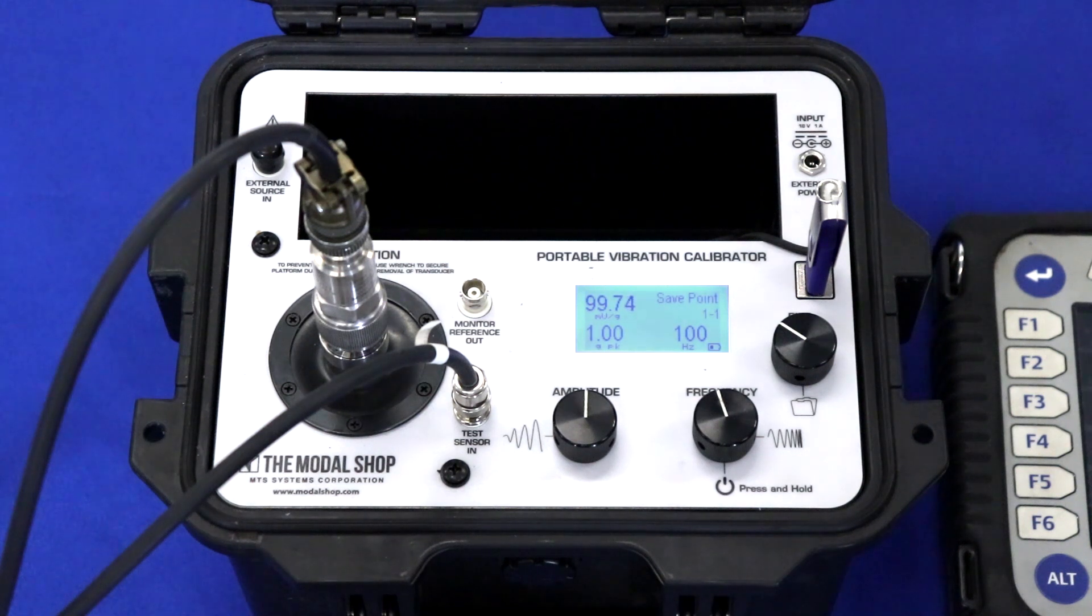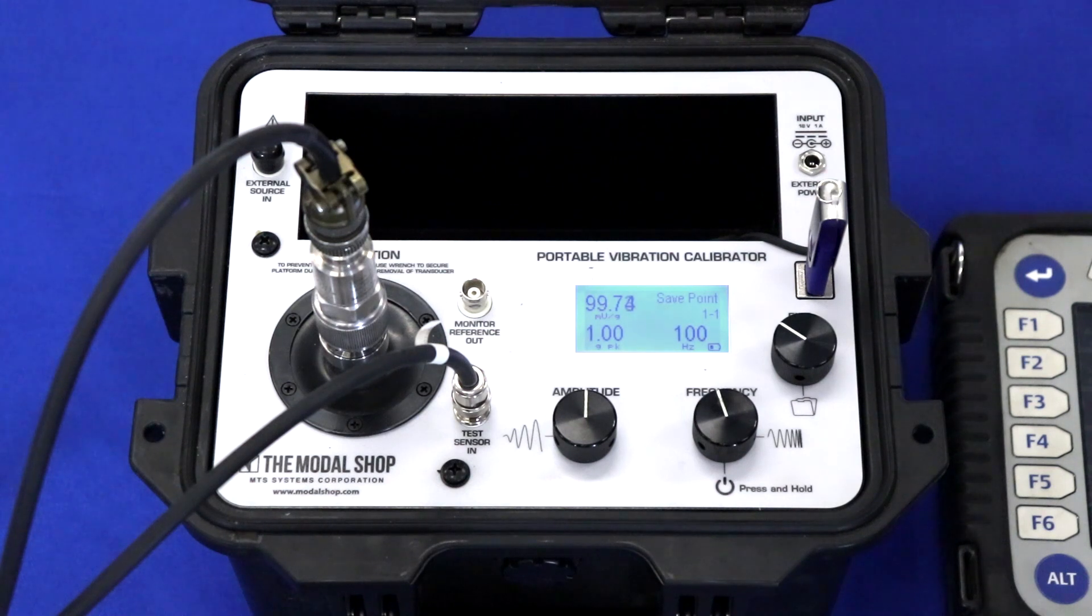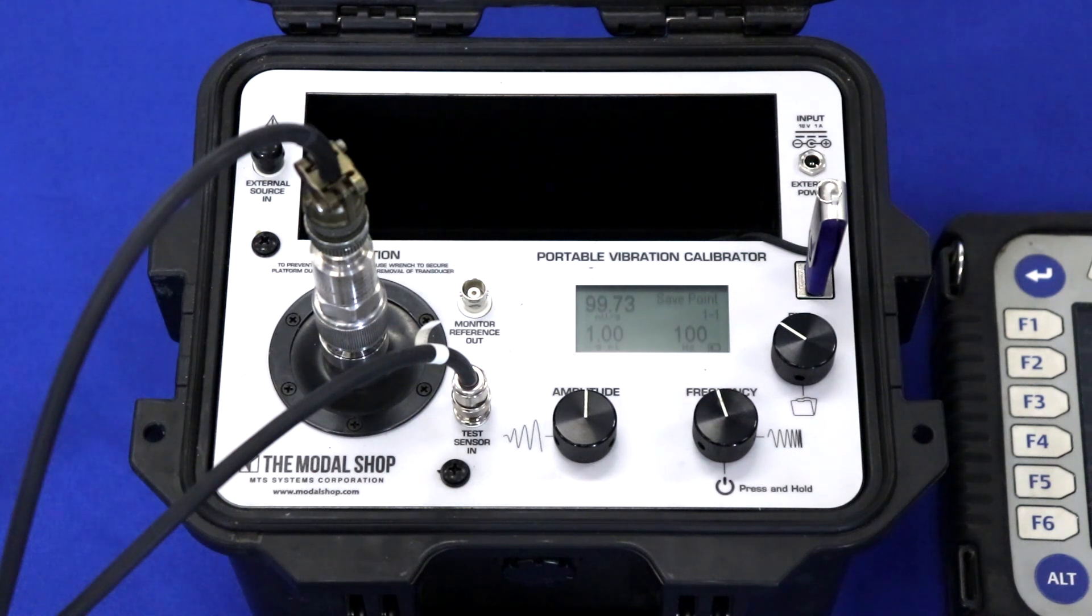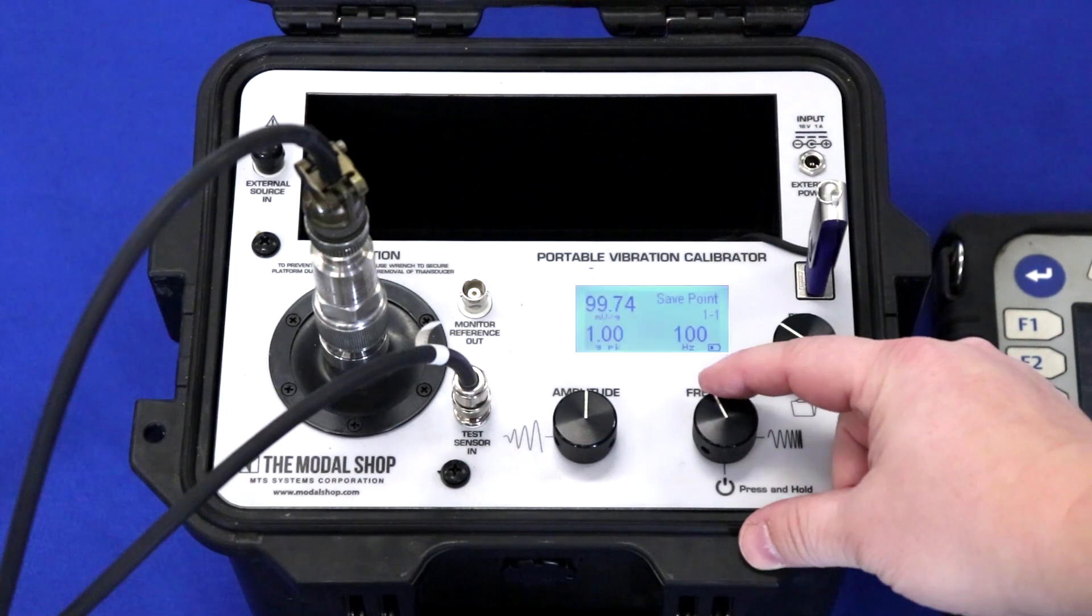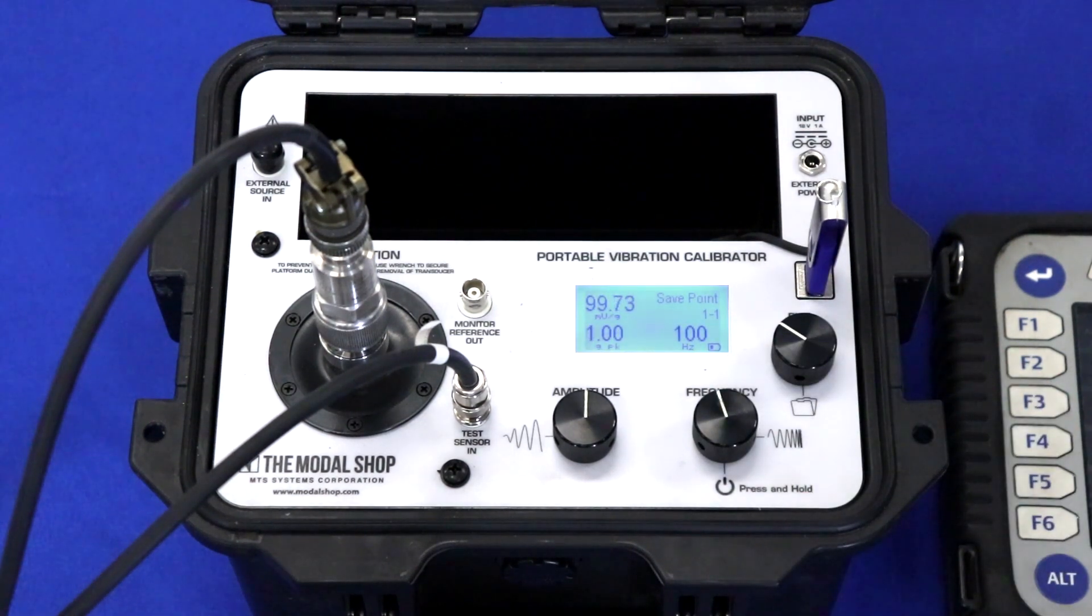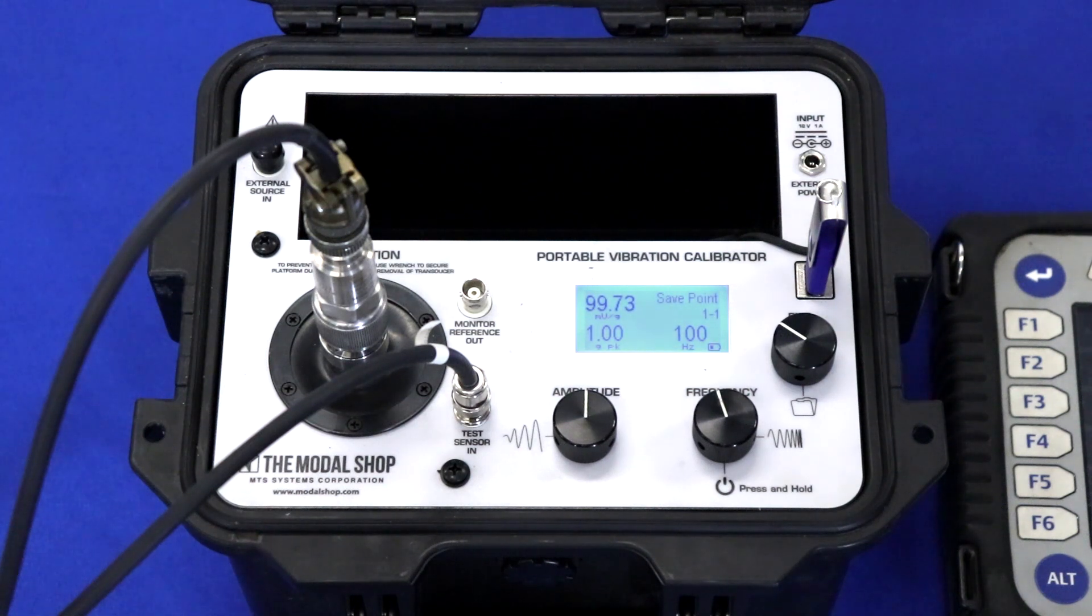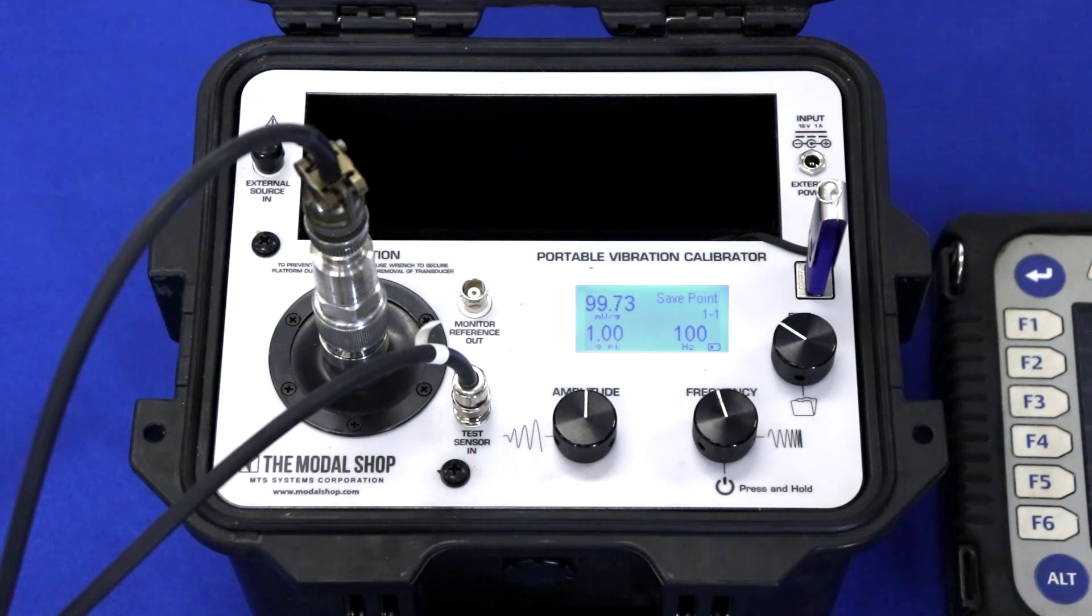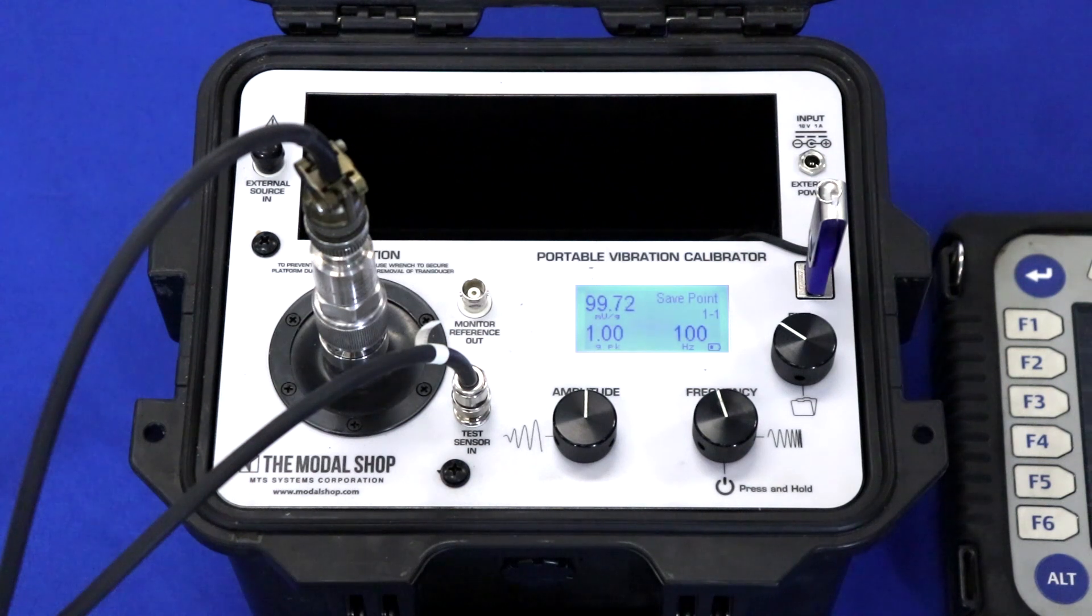The accelerometer and Portable Vibration Analyzer work in tandem to produce quality vibration measurements. So the first step to a good vibration analyzer calibration is to test our accelerometer at some critical frequencies. You can see that my model 622B01 accelerometer magnetically mounted to the shaker is 99.73 millivolts per G.